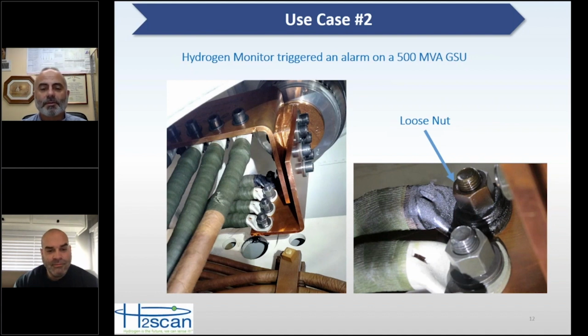They did an internal inspection on the transformer, and the manufacturer sent somebody out, and the guy was in the transformer for about 2 hours, couldn't find anything. And then on his way out of the transformer, he happened to notice that crimp connection, that termination, again at the low voltage lead. At low voltage, you have much higher current than at the higher voltage. There was a loose nut. And so this transformer that was generating a lot of gas was due to a loose nut on that lead, and as that nut was loosening up, the resistance was increasing, and you had lots of overheating of that connection.